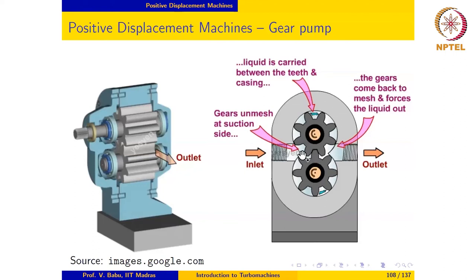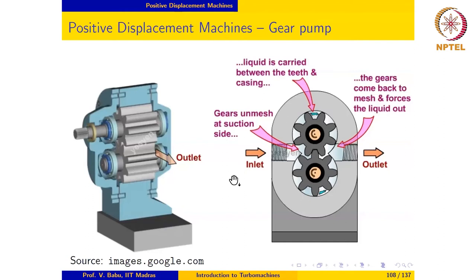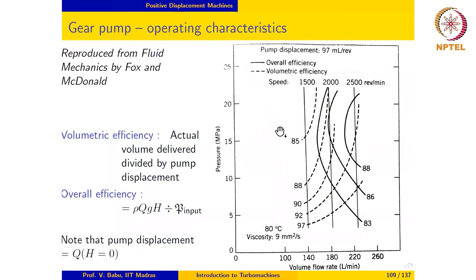Since the displacement volume — the amount of fluid moved from inlet to outlet per revolution — is fixed by the gear geometry, the only way to change the flow rate from such a pump is to increase or decrease the revolutions per minute of the driving gear. If we increase the RPM, more fluid is delivered per minute. If we decrease the RPM, less fluid is delivered. That is the only way to change the flow rate of such a positive displacement pump.